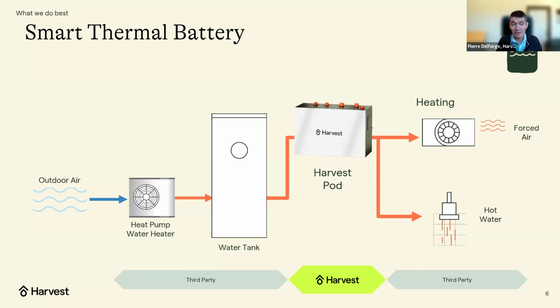So the first thing it does is control when the heat pump water heater runs, turning on and off and how long. That heat pump water heater charges or heats the water in the tank up to 150 degrees Fahrenheit. And basically it's like charging a thermal battery. And that hot water is used for domestic hot water as well as in a hydronic fan coil for forced air heating, or for radiant heat as well, like radiant floors.